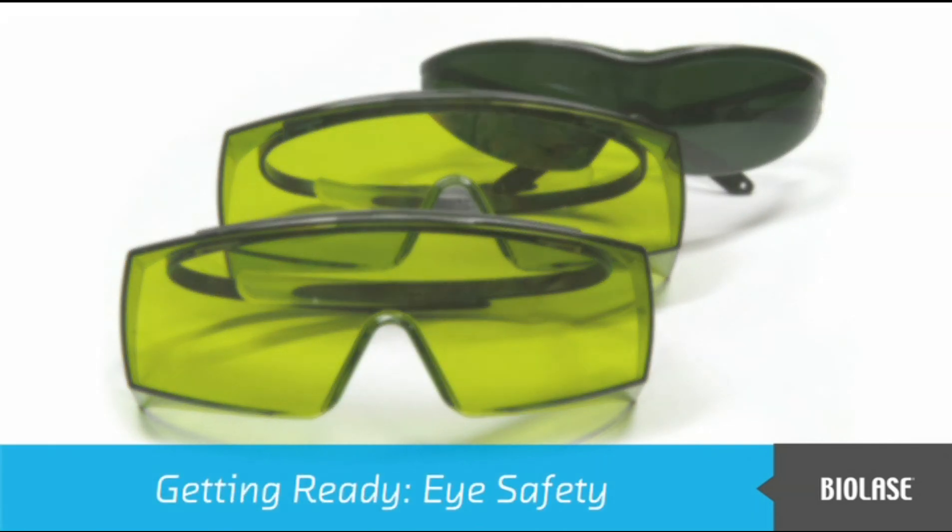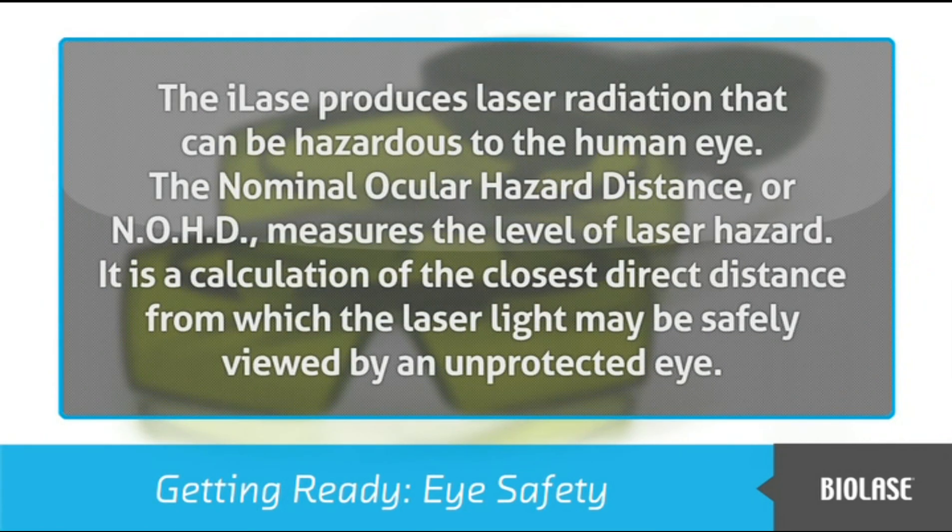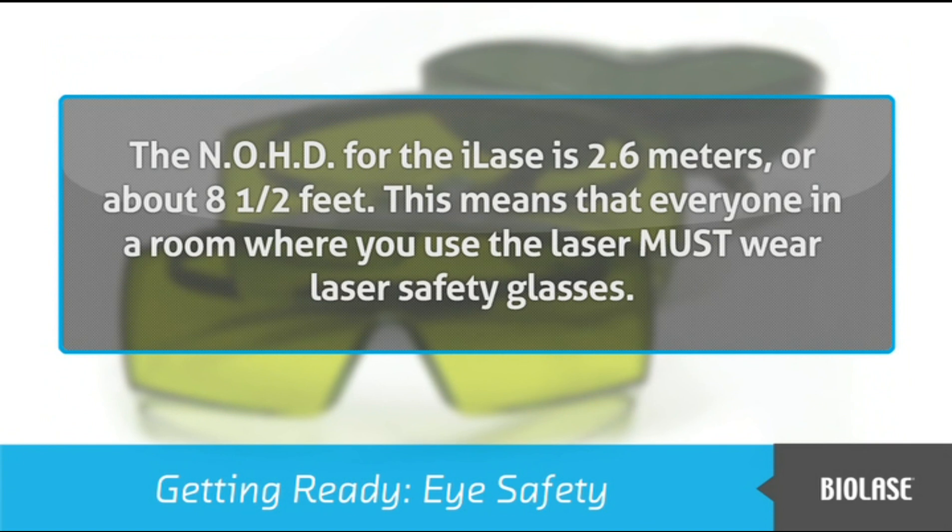Before we start the iLase, there is important information about eye safety that you need to know. The iLase produces laser radiation that can be hazardous to the human eye. The nominal ocular hazard distance, or NOHD, measures the level of laser hazard — it is a calculation of the closest direct distance from which the laser light may be safely viewed by an unprotected eye. The NOHD for the iLase is 2.6 meters, or about 8.5 feet.